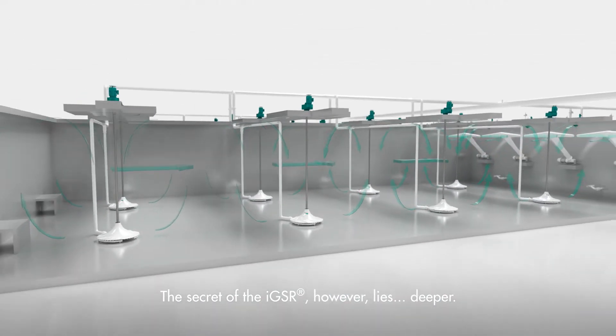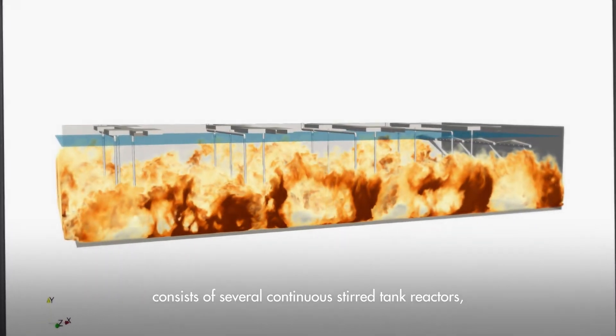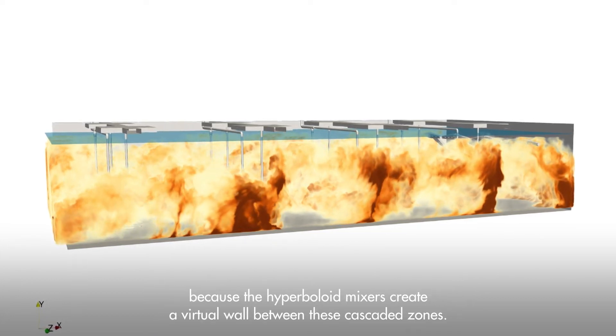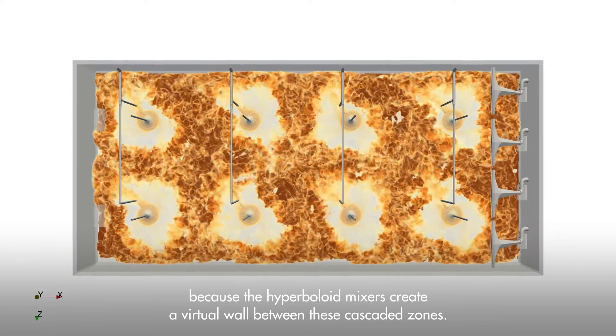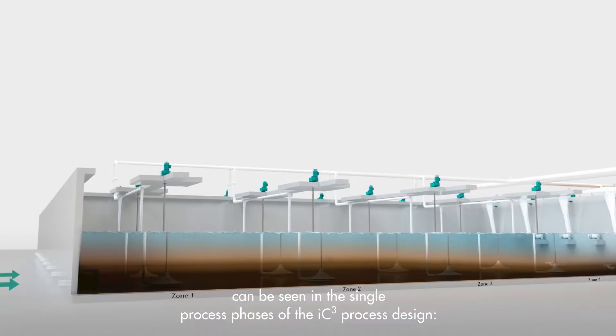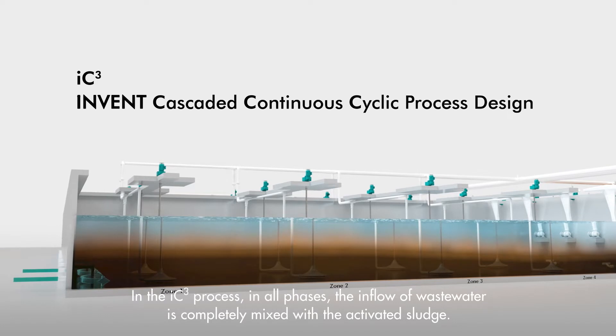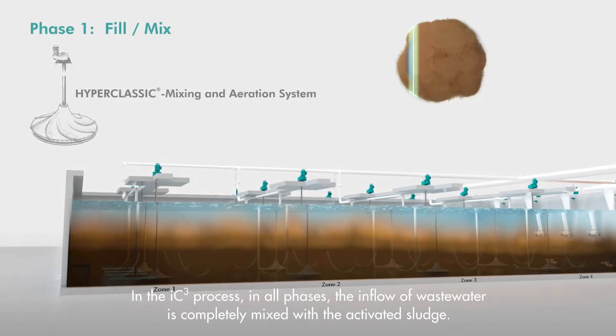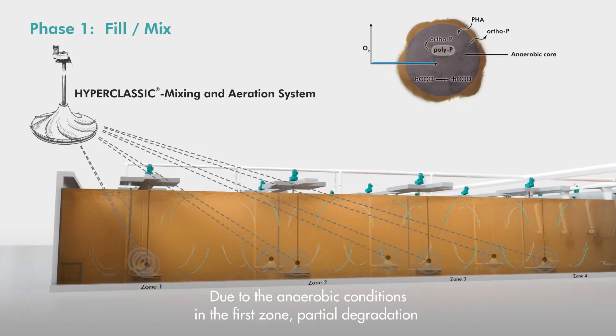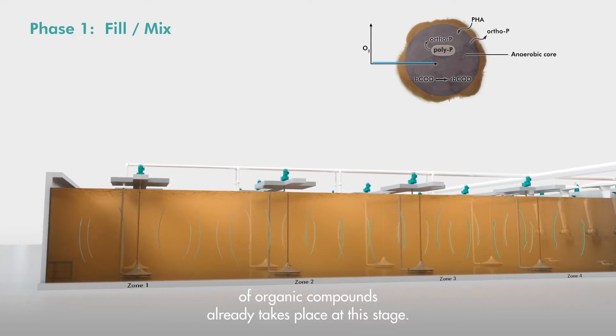The secret of the IGSR, however, lies deeper. In the flow simulation you can see that the basin of the IGSR consists of several continuous stirred tank reactors, because the hyperboloid mixers create a virtual wall between these cascaded zones. How the water moves successively from zone to zone can be seen in the single process phases of the IC3 process design. In the IC3 process, in all phases, the inflow of wastewater is completely mixed with the activated sludge. Due to the anaerobic conditions in the first zone, partial degradation of organic compounds already takes place at this stage.